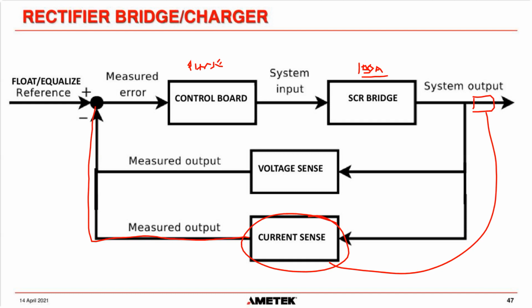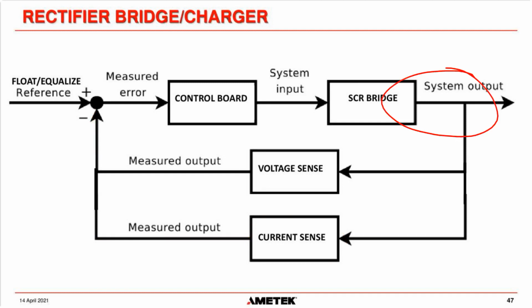So we will keep reducing the system output voltage until we see 100 amps going out through the current sense circuit. That could mean that the voltage goes down to 110 volts. If necessary, it could even go down to 0, I suppose, in theory, but there are many other things that would shut the charger down in that case. But even though it is called current limit and we are limiting the current, we are doing it by controlling the output voltage. Okay, so hopefully that explains a little bit about current limit. And I will try and do another webinar that goes into current limit a bit further in depth.